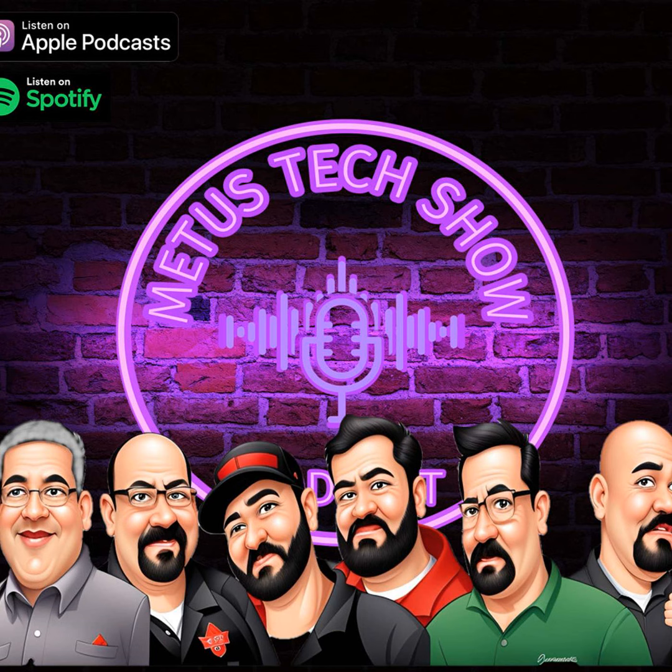Something that I always like to bring up when you're in that situation, Paul, you mentioned being on call. I like to use the journalistic approach, which is the who, what, why, where, when, and how. If somebody gives me a call and I want to know what equipment they have, and we're going to be focusing on Mitsubishi equipment today. How long ago was the system installed? What's the chief complaint? Let's say the chief complaint is not heating.